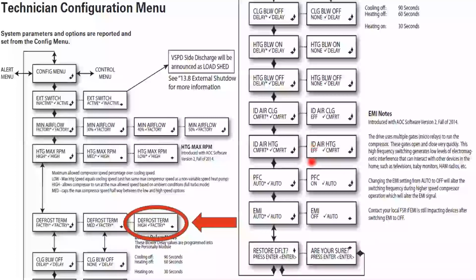We have seen a couple of systems come from the factory set for efficiency, and our static could be too much, or we're not getting a good delta T. You may have to go in here and adjust it to comfort to lower that indoor fan speed. So keep that in mind.